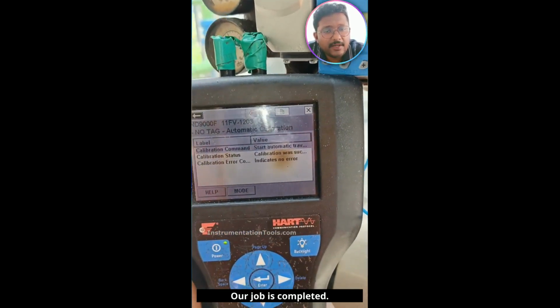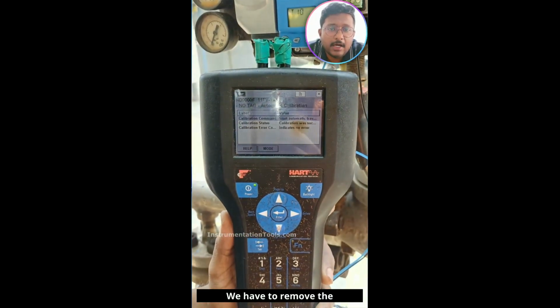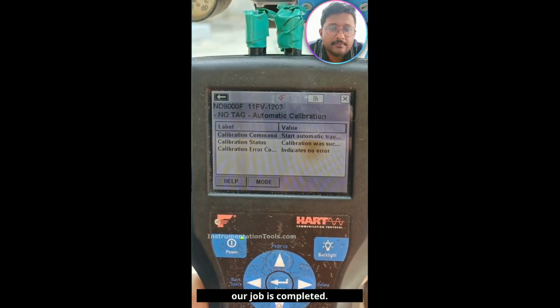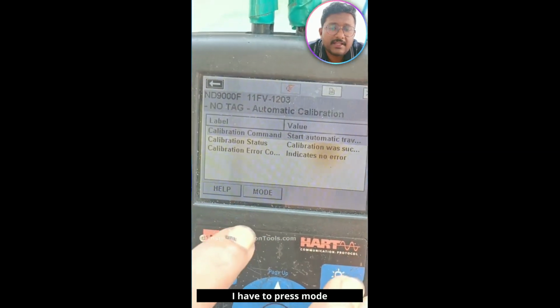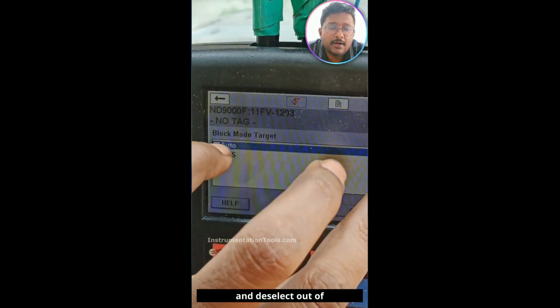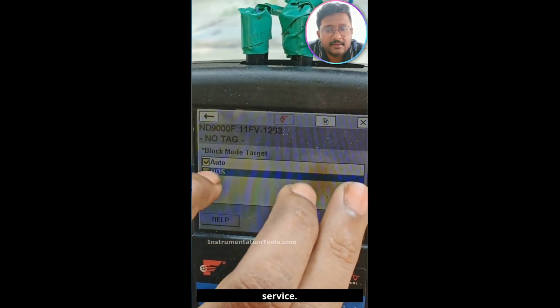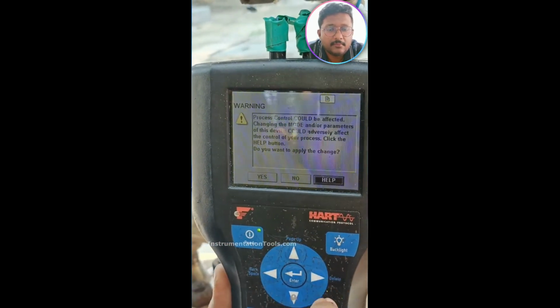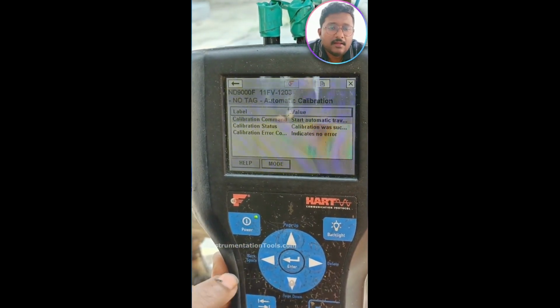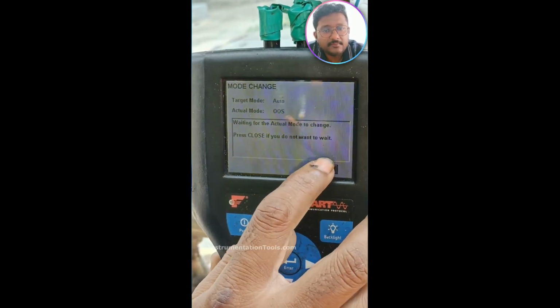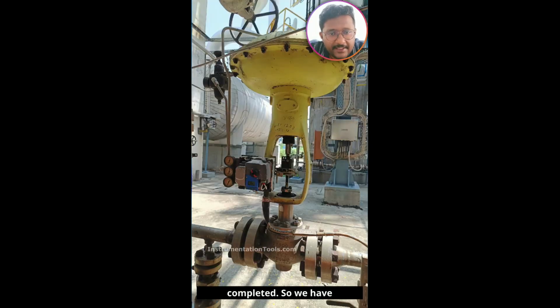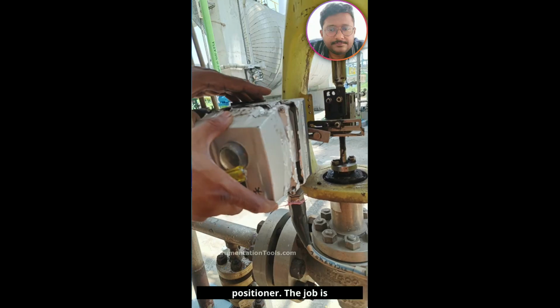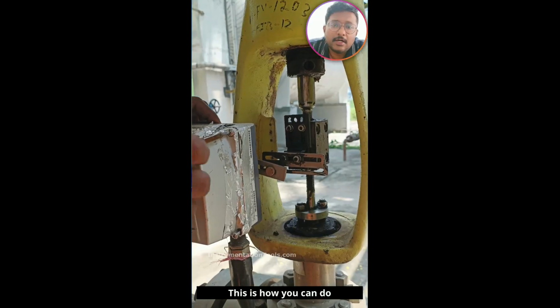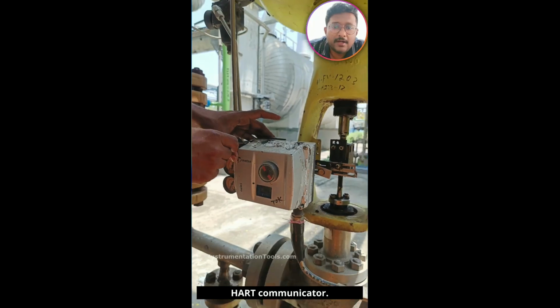calibration was successful. Remember, our job is completed, but we have to put the mode again in auto mode. We have to remove the out of service because our job is completed. I have to press mode again and select auto and deselect out of service OOS. Okay, yes, that's it. The calibration is completed. So we have to remove the HART communicator and again we have to cover the valve positioner. The job is completed. This is how you can do the control valve calibration using your HART communicator.